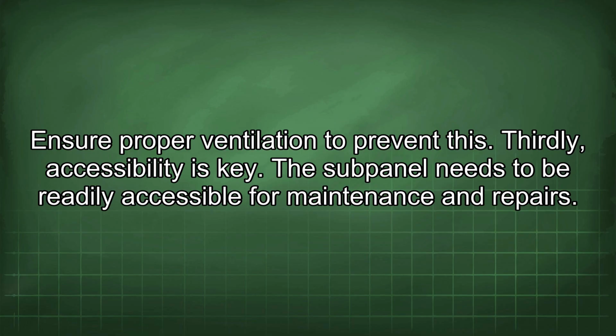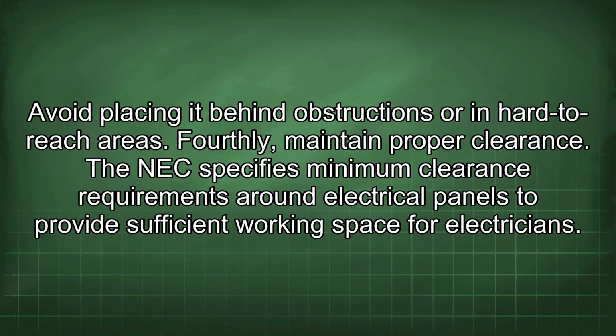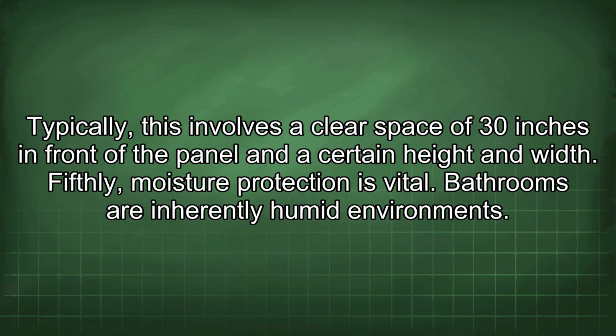Thirdly, accessibility is key. The subpanel needs to be readily accessible for maintenance and repairs. Avoid placing it behind obstructions or in hard-to-reach areas. Fourthly, maintain proper clearance. The NEC specifies minimum clearance requirements around electrical panels to provide sufficient working space for electricians. Typically, this involves a clear space of 30 inches in front of the panel and a certain height and width.